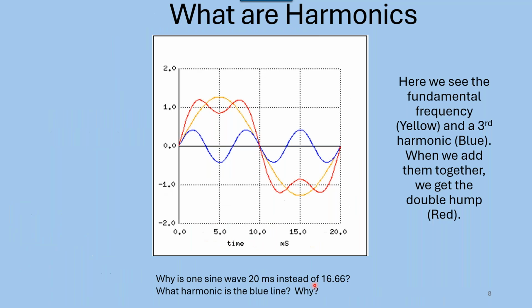This is an interesting slide that I've got. What I've got here in the yellow, that's our fundamental frequency, okay? And then what I've shown is a third harmonic. With harmonics, it actually occurs in the same time period as the fundamental. But with a third harmonic, I'm going to have 1, 2, 3 cycles in the same time that I've got this one harmonic or one cycle.